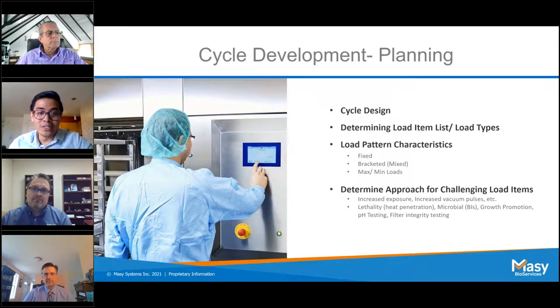Next, in regards to looking at the approach for challenging load items based off statistical and physical analysis, typical approaches for challenging load items are commonly done through analyzing lethality or heat penetration, and microbial or BI testing. When using liquid cycles, you would typically use ampule BIs for your tests, whereas for vacuum or gravity cycles, you would typically use BI strips. Other approaches also used in industry involve growth promotion, pH testing, and filter integrity testing.